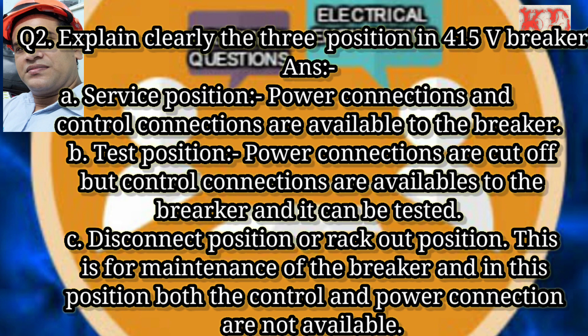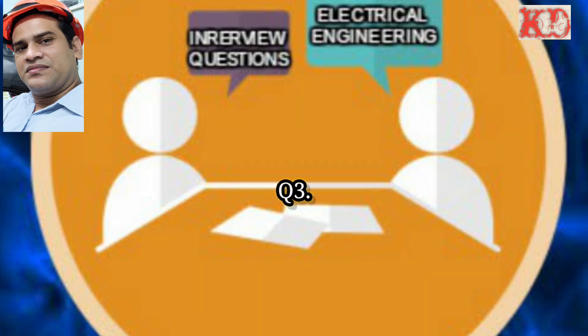Third, disconnect position or rack out position: this is for maintenance of the breaker, and in this position both the control and power connections are not available. These were the three positions of the breaker — first service position, second test position, and third rack out position.